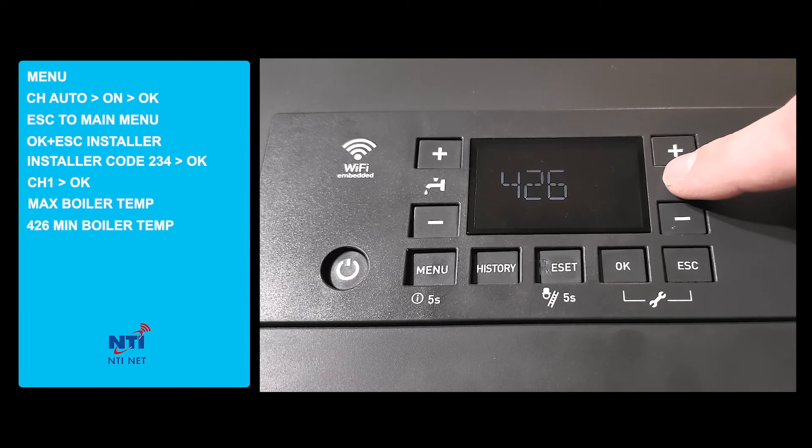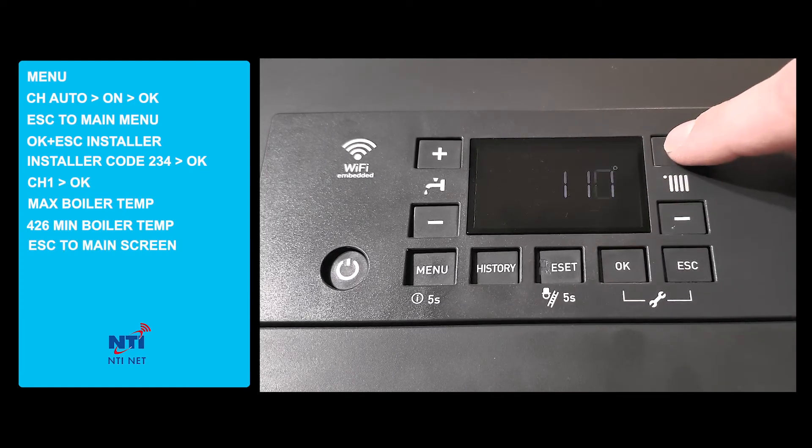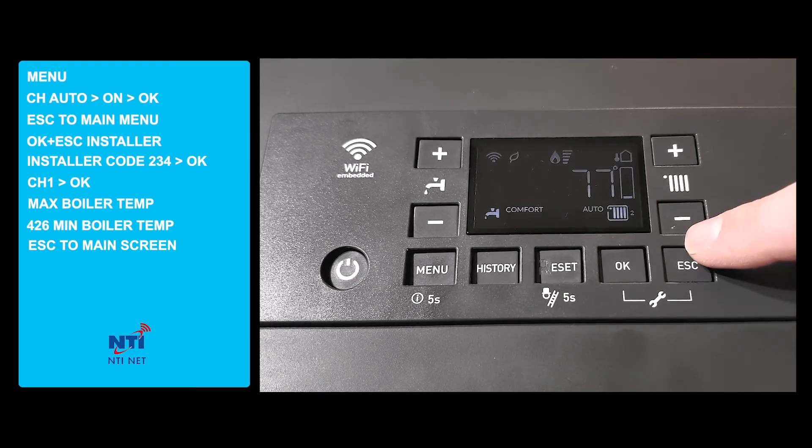And 426, which represents the minimum temp, which we'll set to 110 and press ok. We've now set up the TRX to operate with outdoor reset between 110 and 175 degrees. We'll see you in the next video.